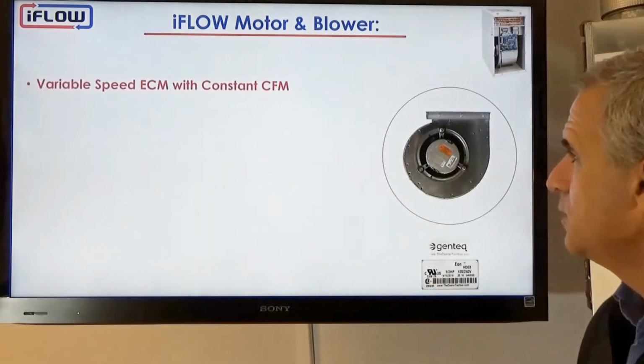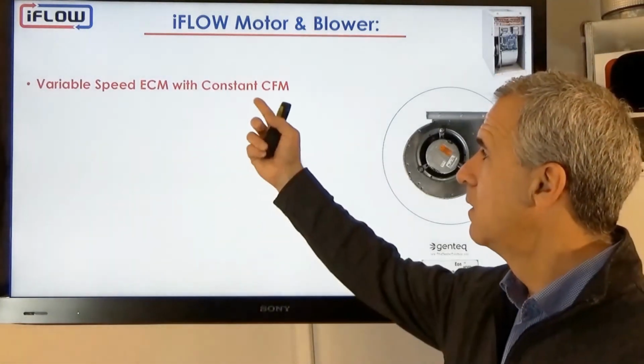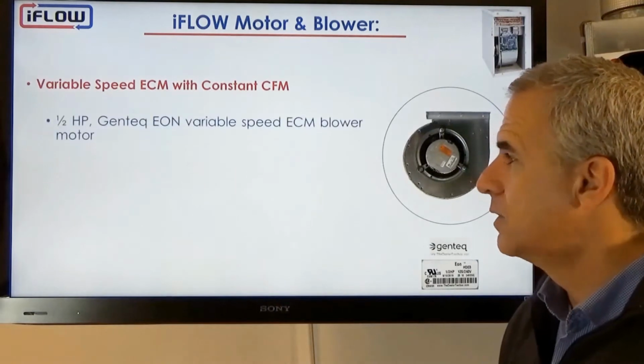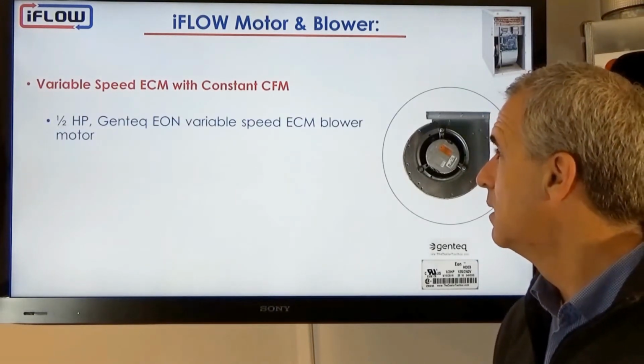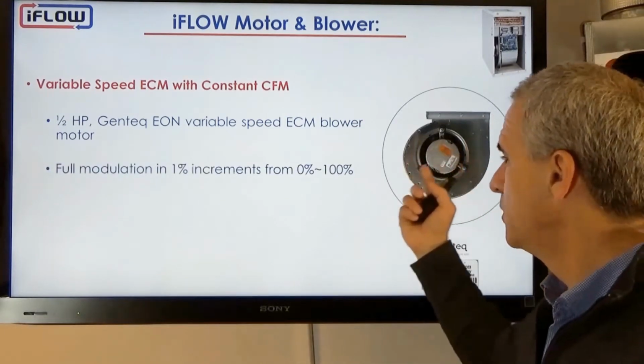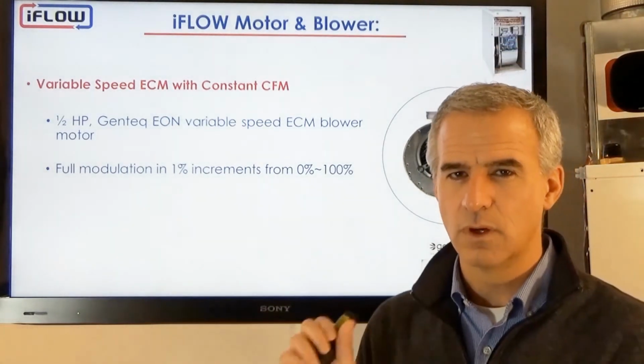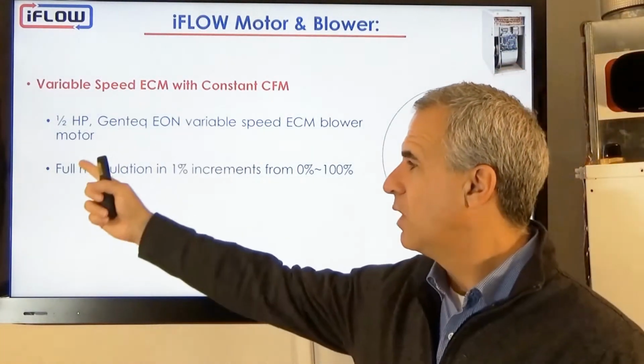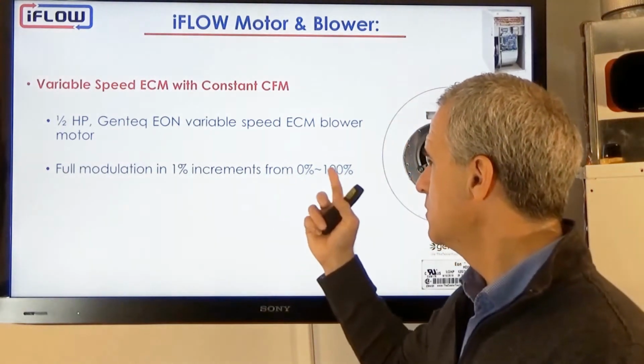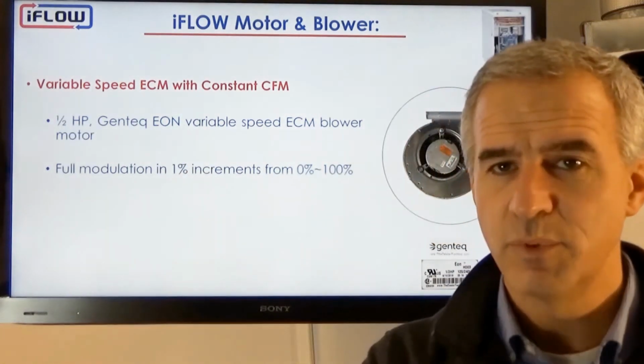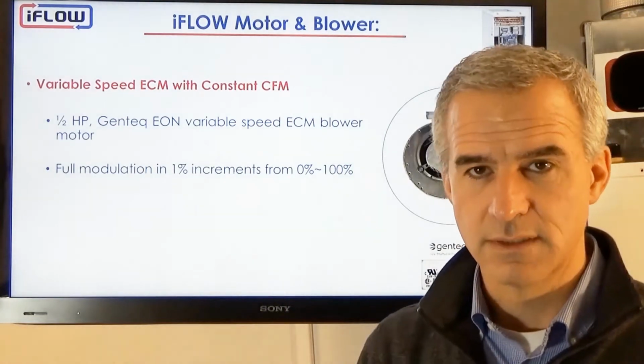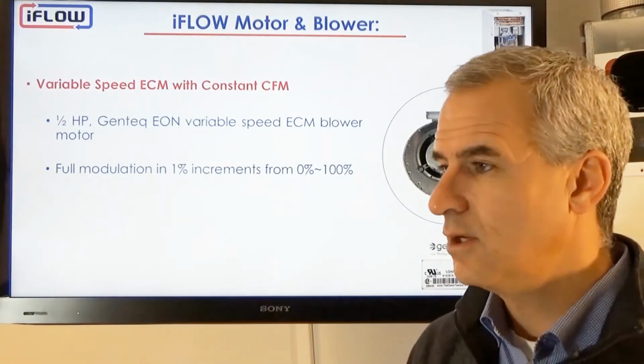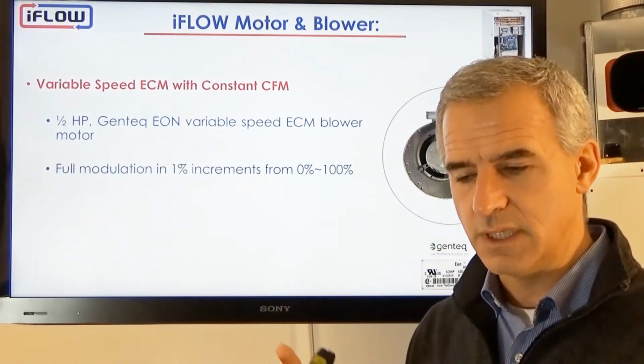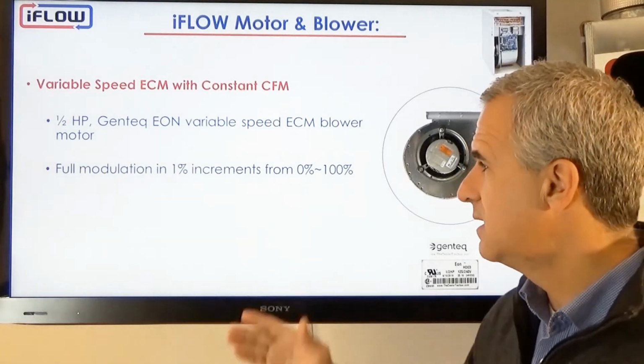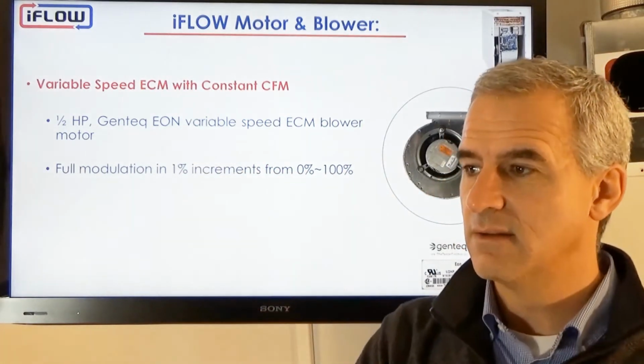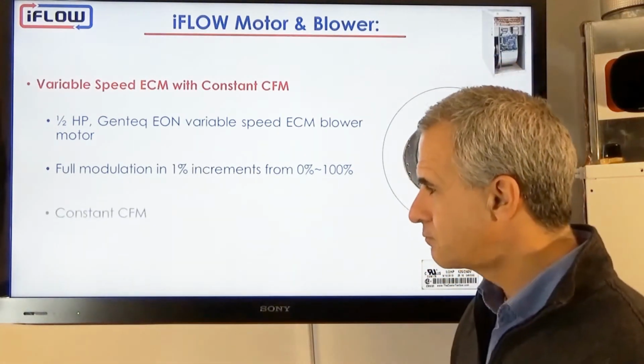To make that happen, we're using a variable speed ECM blower with constant CFM capability. We're using a 1/2 horsepower Genteq Eon variable speed ECM blower motor. For those who are familiar with the Genteq, if you have any of the Genteq diagnostic tools, they will work on this blower as well without problem. And then we modulate that. Our controller modulates the fan from 0 to 100% in 1% increments. So I can give you 5%, I can give you 40%, I can give you 80% or 100%, whatever the controller deems it needs based on the inputs from all of the sensors. We then tell the blower to come on at whatever the demanded flow rate is, and we deliver that precisely.